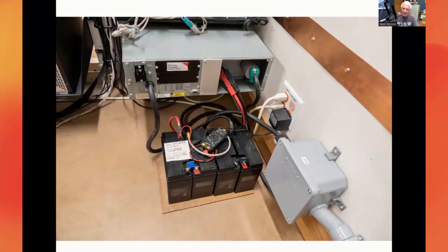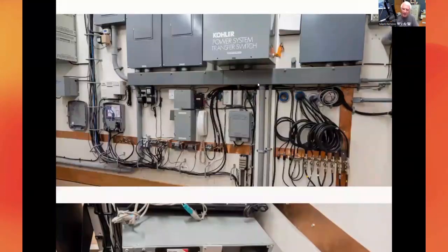Now, the UPS can be disconnected easily. On this box on the right, you'll see that's city power or the building power being delivered to the UPS. The UPS plugs into it. And then there's a cable out of the bottom of this UPS box, and it plugs into the UPS. So if for some reason the UPS fails completely, I can in seconds bypass it by just unplugging one and plugging the other one in.